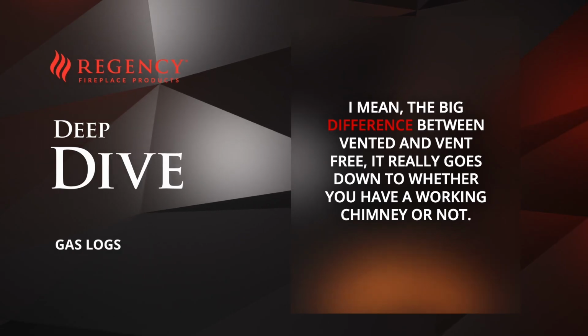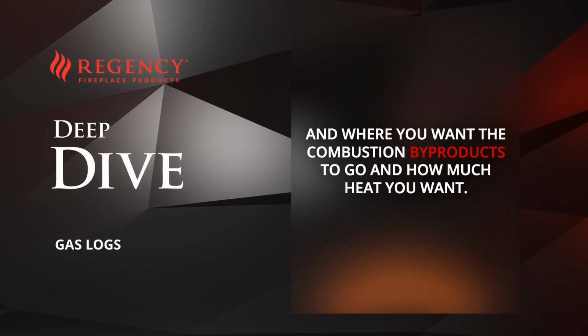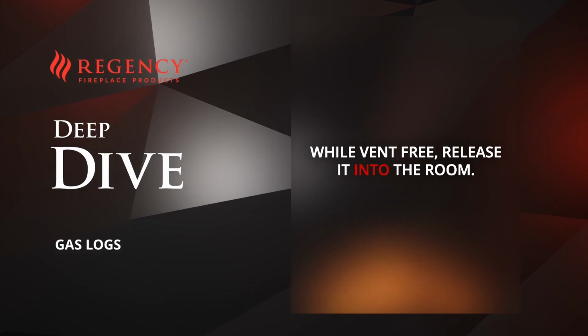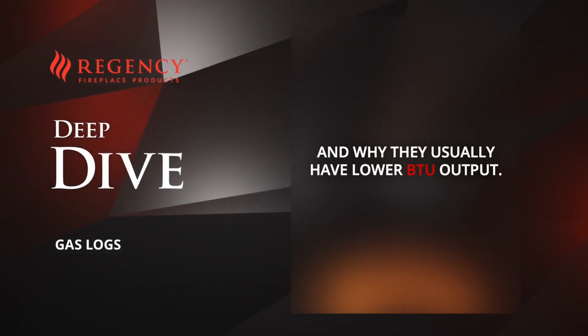Absolutely. I mean, the big difference between vented and vent-free really comes down to whether you have a working chimney or not. Right. And where you want the combustion byproducts to go. And how much heat you want. Exactly. Vented logs send that stuff up the chimney, while vent-free release it into the room. And that's why there are those restrictions. Right. And why they usually have lower BTU output.